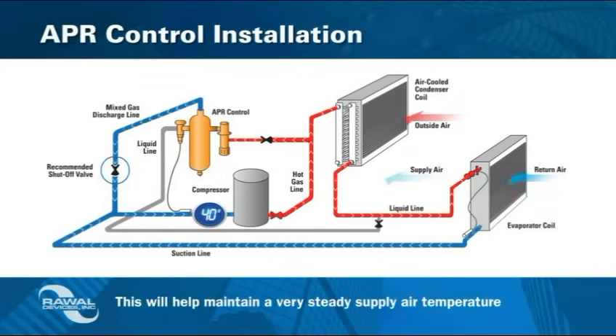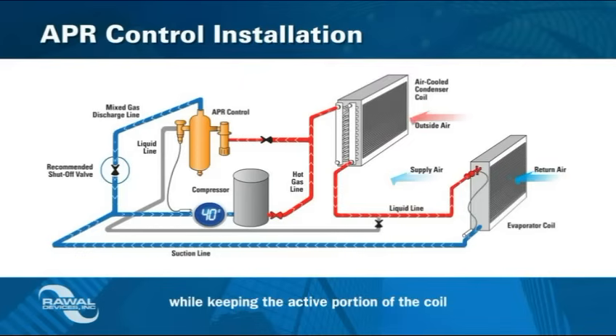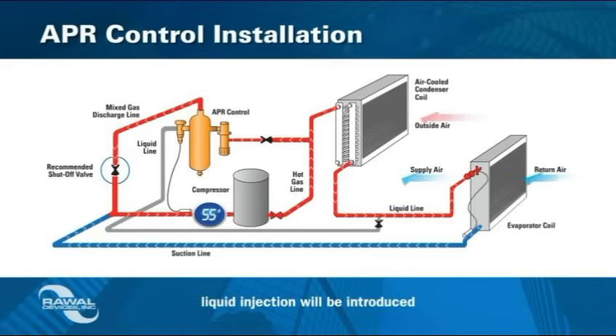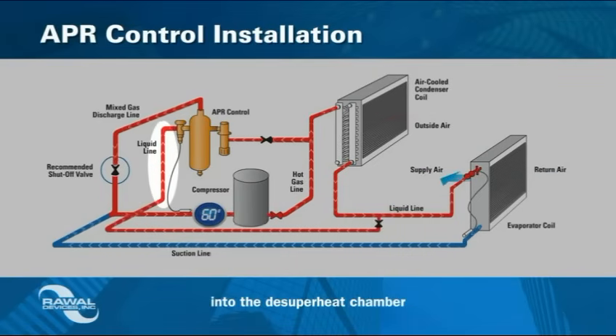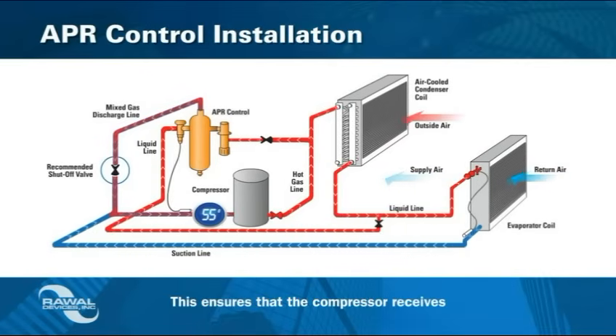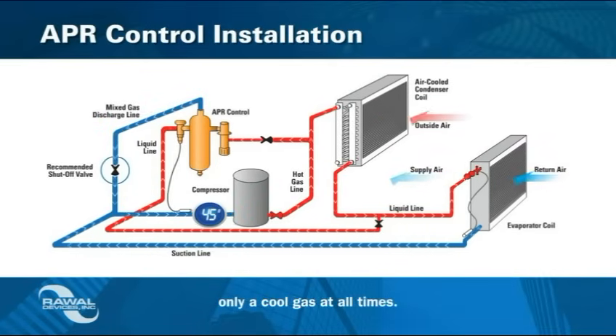This will help maintain a very steady supply air temperature while keeping the active portion of the coil in the dehumidifying mode. As added protection for the compressor, liquid injection will be introduced into the de-superheat chamber if the suction line gas becomes heated enough at deep modulation to adversely affect the compressor superheat. This ensures that the compressor receives only a cool gas at all times.